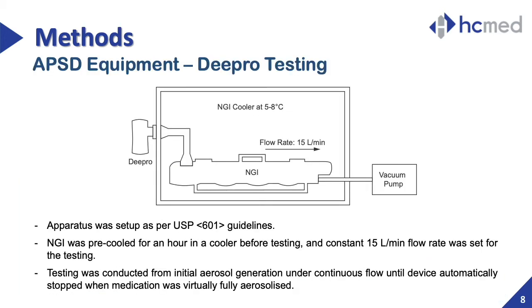We prepared two configurations for the NGI testing. Firstly, according to the guidelines, for a nebulizer in continuous output mode like Deepro, a pre-cooled NGI impactor and USP throat were set up with a vacuum pump operating at 15 liters per minute to conduct the APSD test. After checking the flow rate with a flow meter, Deepro was directly connected to the mouthpiece adapter of the NGI and started aerosol generation. When the medication was fully nebulized, the device was then automatically turned off.